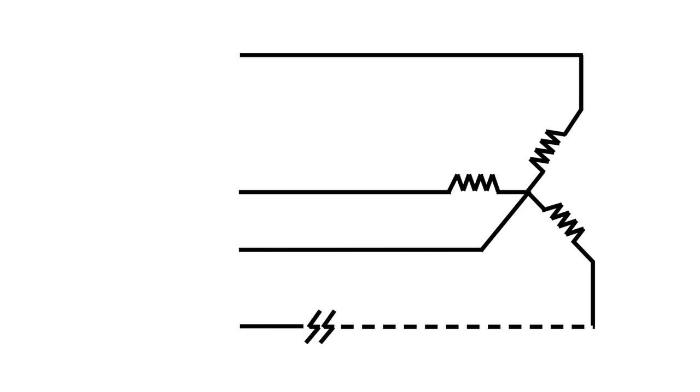Let's start adding some values to these. At this point here with this broken line down here, we will have 120 volts to ground or to neutral on this load, 120 volts ground to neutral on this load, and this side here will not see any voltage because the line voltage coming in is nonexistent because of that break.